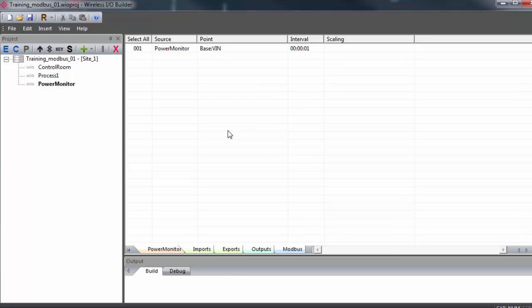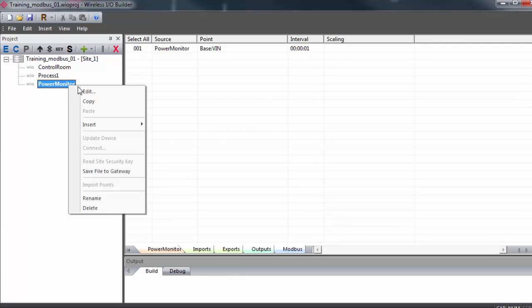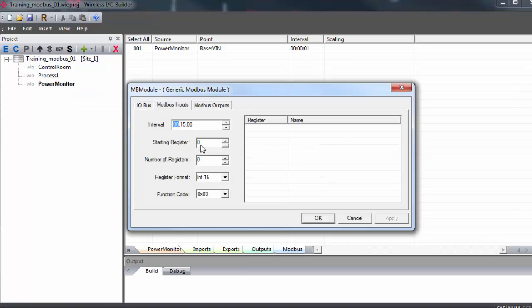The RTU settings will have to match the configuration of the slave device that we're connecting to. Now, instead of adding I.O. modules to this gateway, we'll add a Modbus module. So with the power monitor selected, hit the plus icon or you can right click. Go down to insert and select Modbus module.